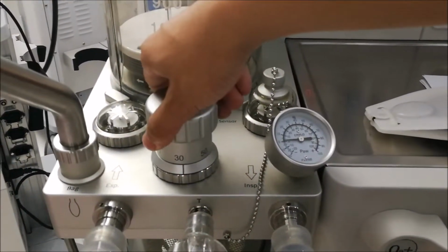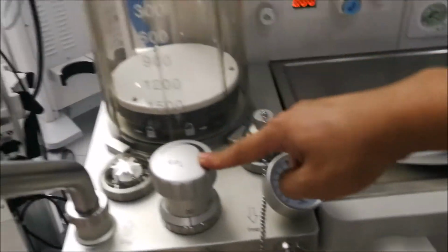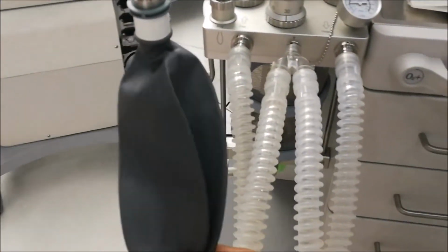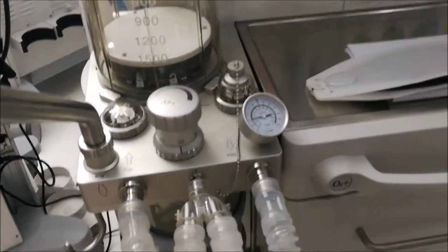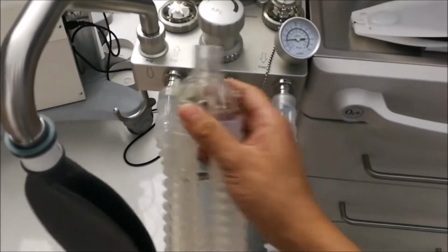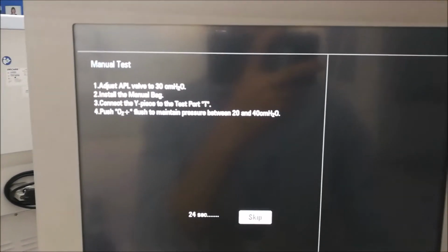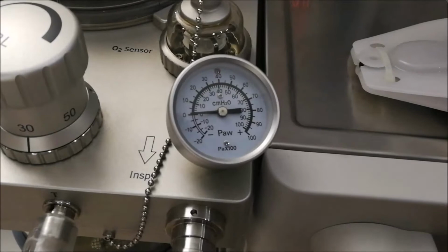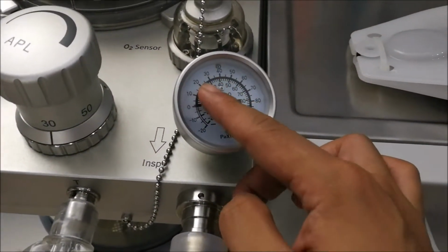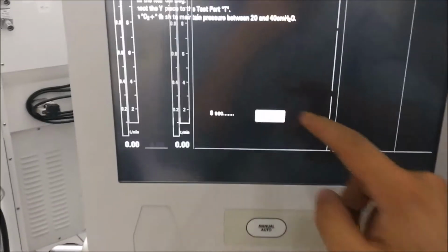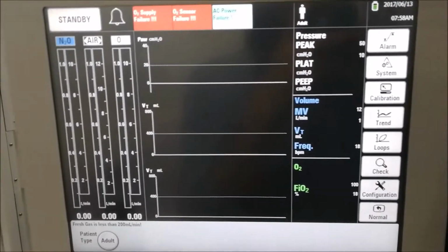And second is the manual test. First, adjust the APL valve to 30 cmH2O. Okay, 30. This is the APL valve. And second, we can install the manual bag. This one is the manual bag. Here, this one, manual bag. And the third is the Y-piece. This is a tube. And we connect this white piece to this T-port. And then push oxygen to 20 to 40. That means we just push it and make the pressure gauge to 20 to 30 and keep it. It will pass. Okay, now we haven't it, so we just skip it.